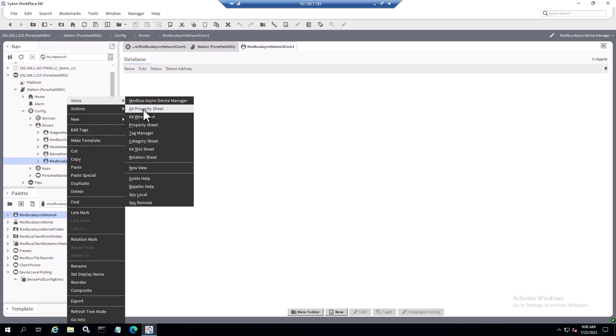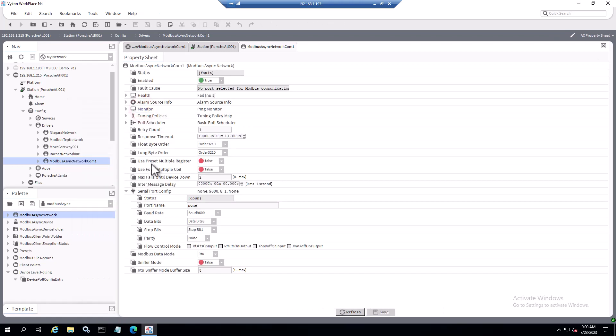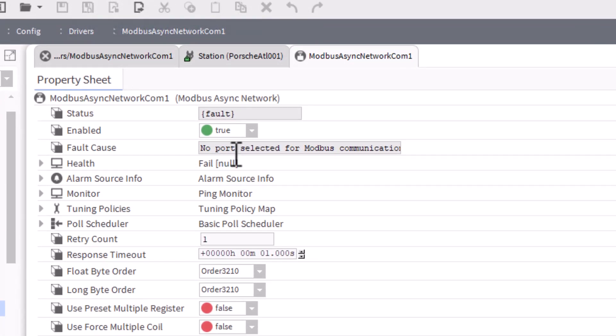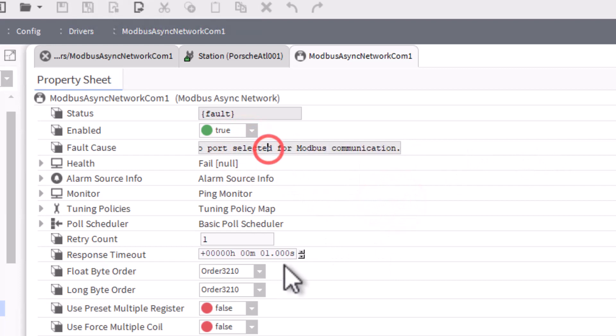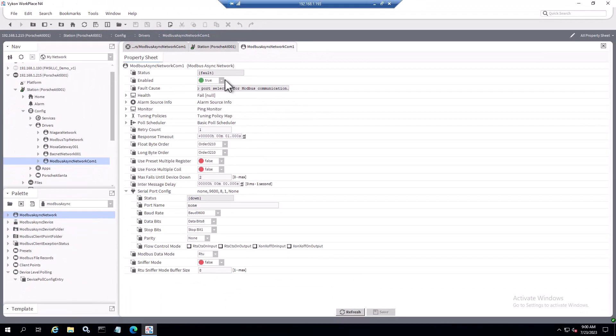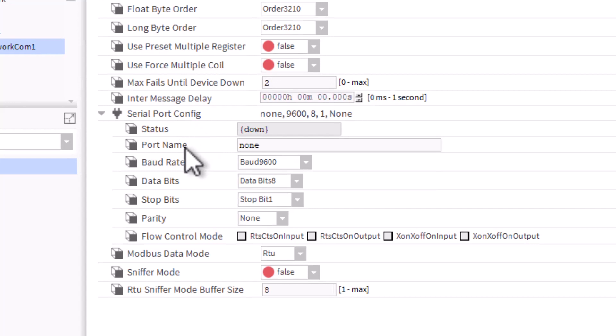Once the sheet opens, we can see that we have a fault coming through on the status and it says no port selected for Modbus communication. To correct that, we just have to designate the COM port name. On the Jace 8000 you have COM1, COM2, and then if you're using the RS485 add-on cards, you would designate COM3, COM4, COM5, COM6 depending on how many modules you have connected. I'm going to come down to the serial port config and here you'll see port name says none. This is what breaks that initial communication when you deploy this network.